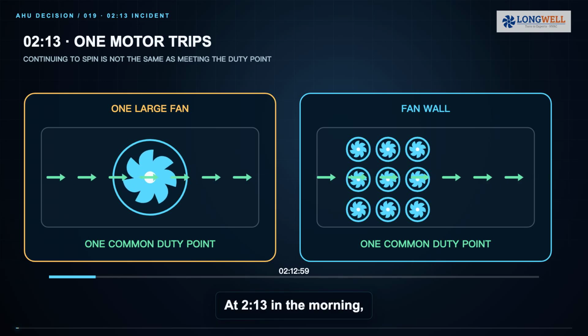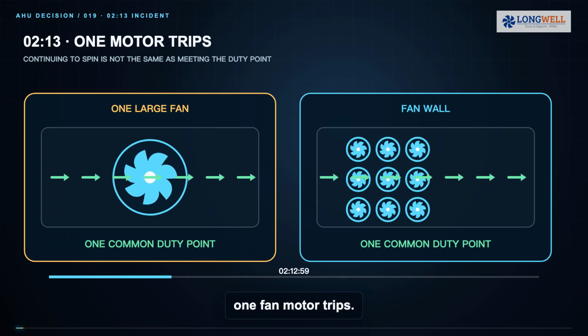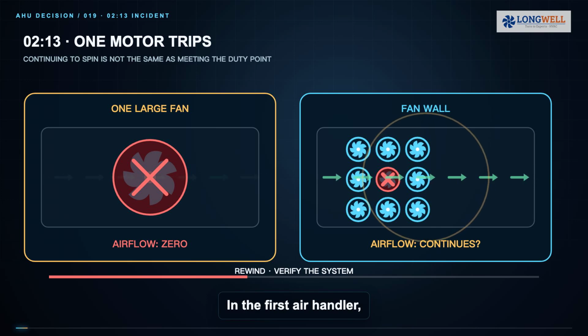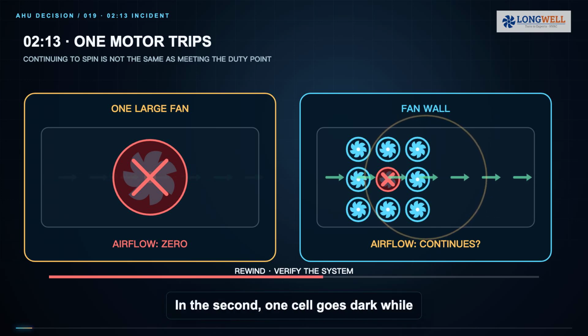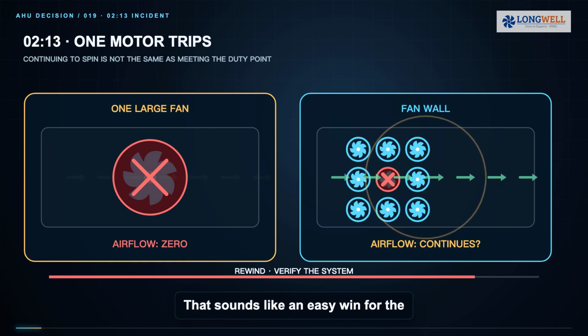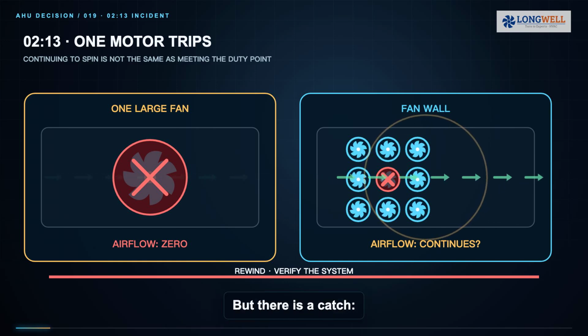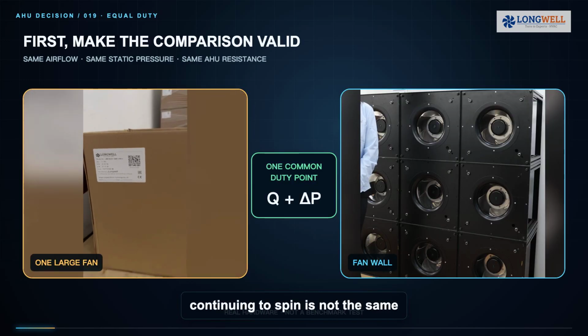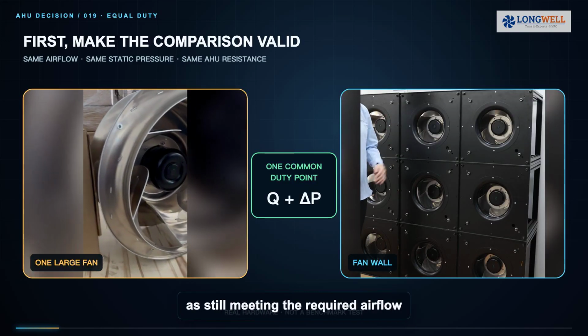At 2:13 in the morning, one fan motor trips. In the first air handler, airflow falls to 0. In the second, one cell goes dark while the other modules keep running. That sounds like an easy win for the fan wall. But there is a catch: continuing to spin is not the same as still meeting the required airflow and pressure.